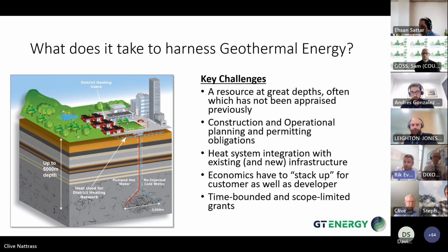When you start to remove the water, the pressure drops down and your ability to produce more water in the future is impacted. If we re-inject the water, we keep the pressure up in there and you ensure that you've got a long-lived system. There are plants operational today which were drilled over 100 years ago, just demonstrating that longevity really is deliverable.